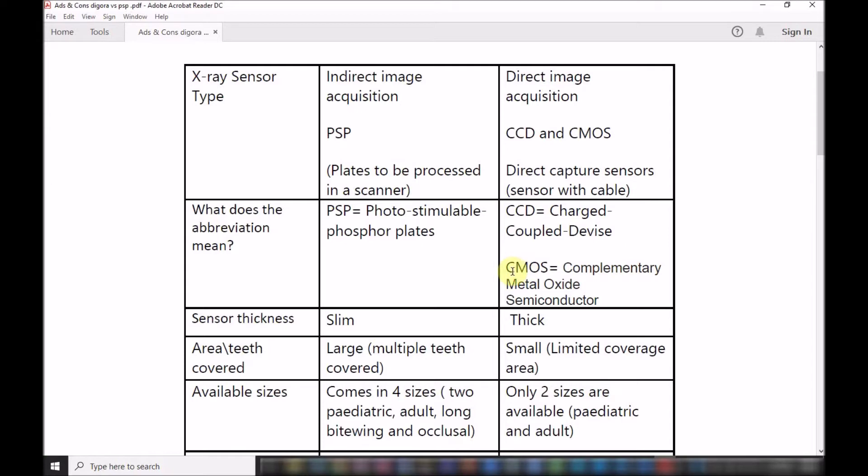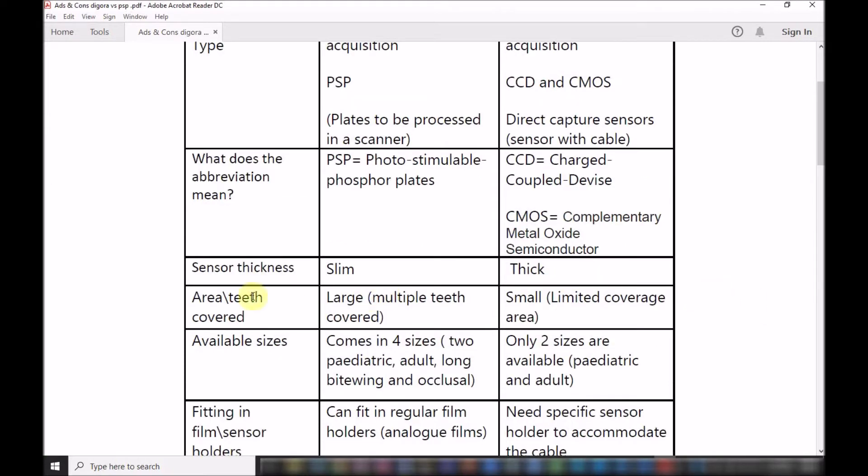When it comes to sensor thickness, these are always slim because it's a plate that is coated with phosphor. While the direct image sensors are thick in most cases, however many companies are trying to reduce the thickness. But again, it is thicker than the indirect plates. The thick direct sensors actually have all the image capturing and rendering to light and then to computer language done within the sensor itself.